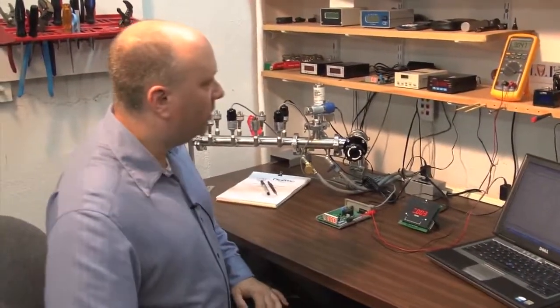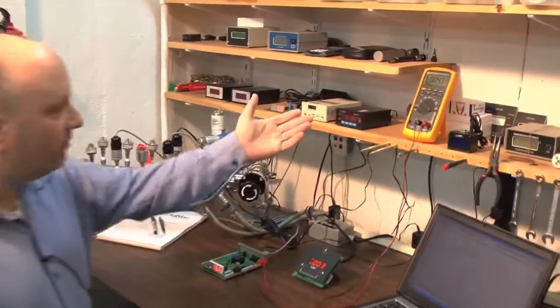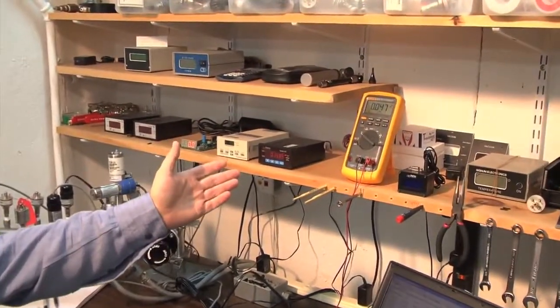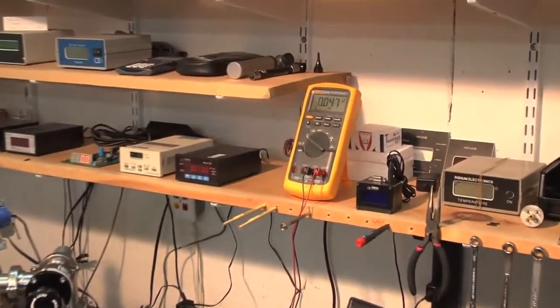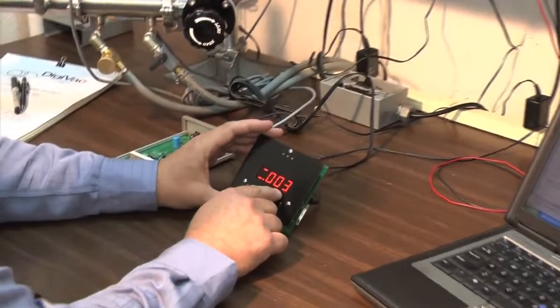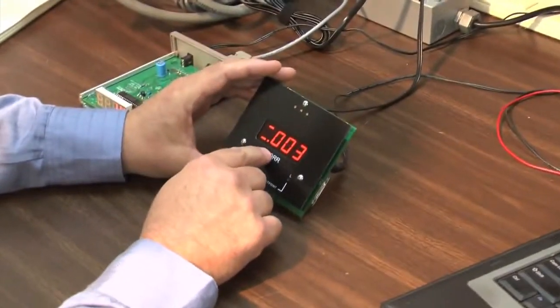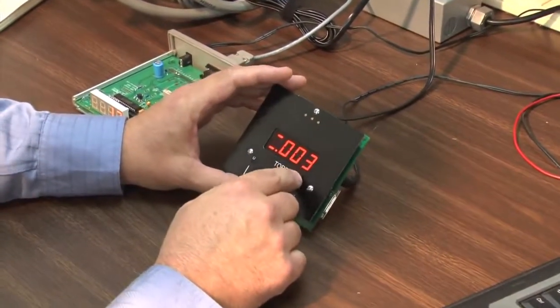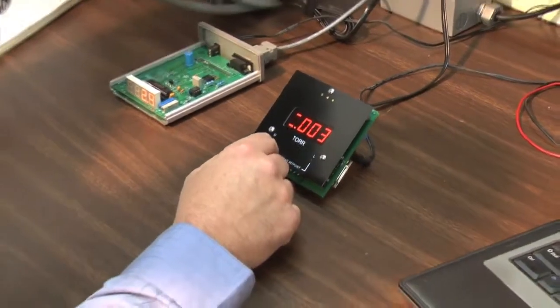And of course, our third instrument we use is a voltmeter. It's a common voltmeter but it's been calibrated to NIST traceable standard. Our 801W instrument is already under vacuum. We can see it's given a good reading. It has two active set points but of course it's not properly calibrated compared to the reading on our Convectron.